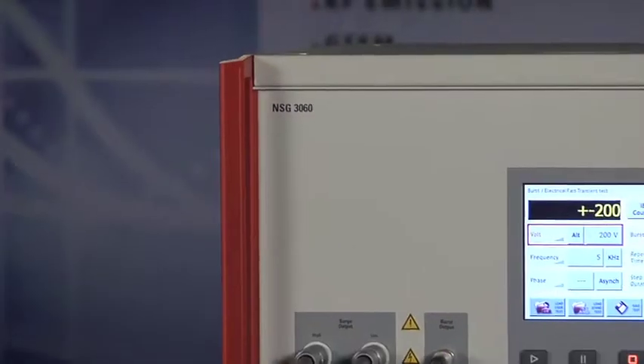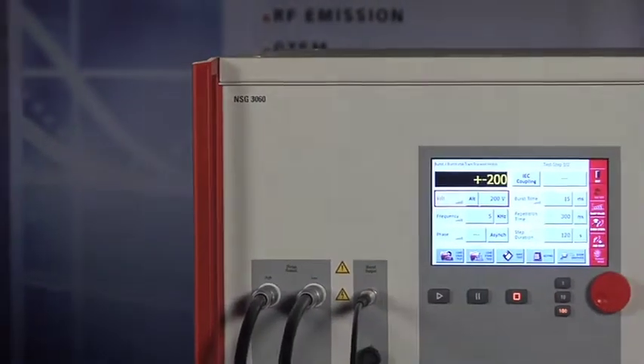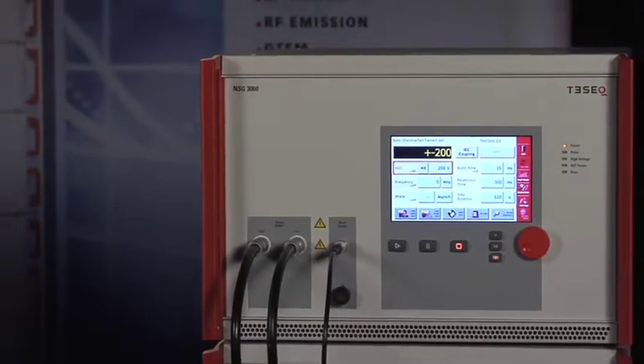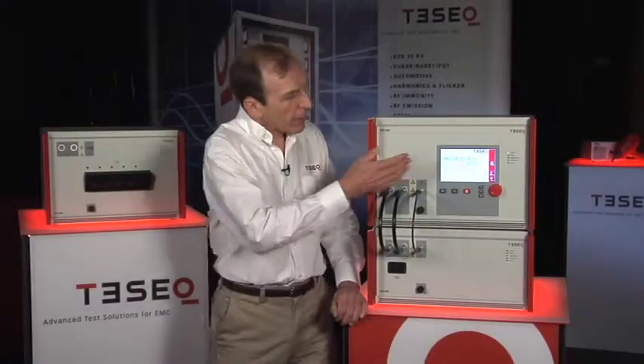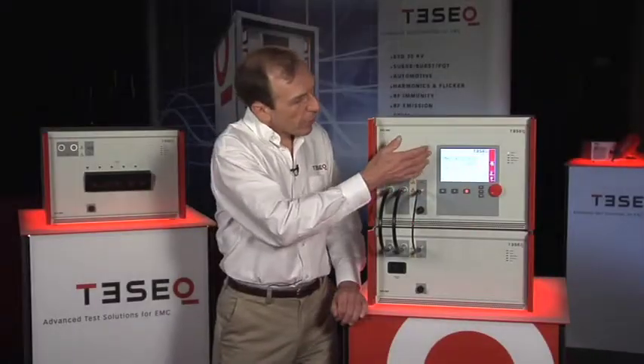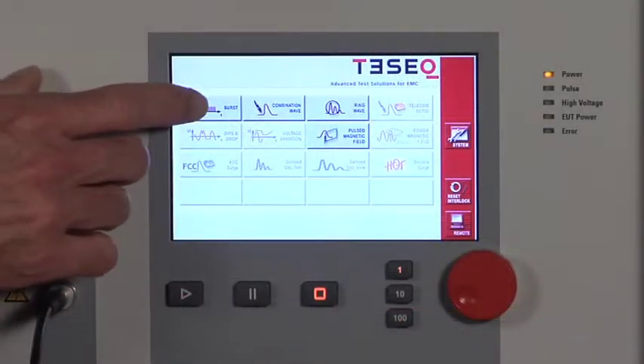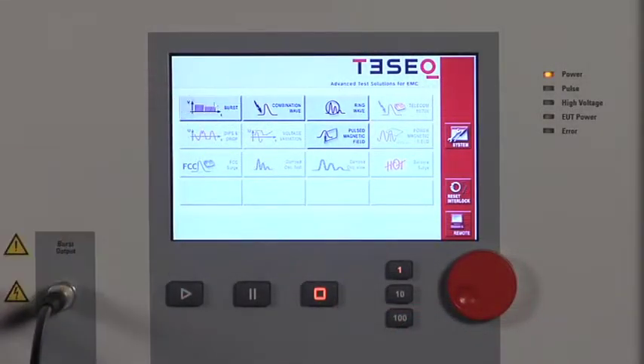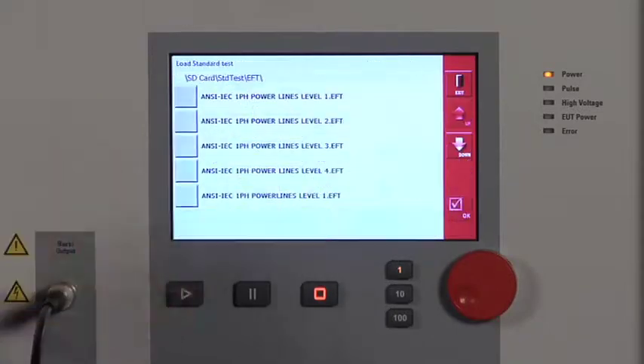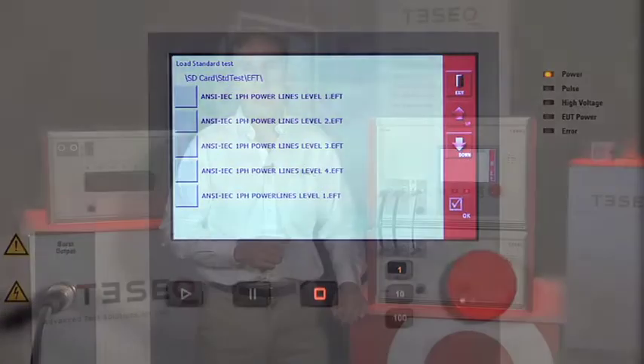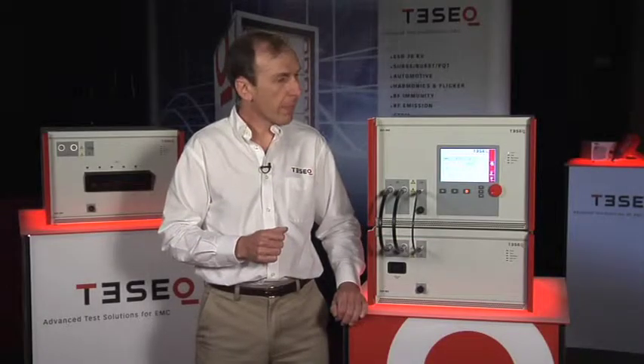The system is modular. It can be configured with any one of these capabilities individually or in combination. It has a 7-inch color LCD touchscreen for its user interface. It has the capabilities to generate surges to 6.6 kV or even higher, fast transients to 4.8 kV, and dips and interrupts up to 16 amps.